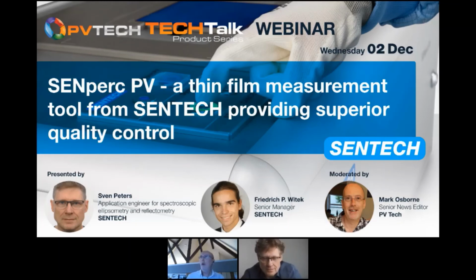Okay. Well, looking at the time, maybe just a few quick questions that I can fire at you. So obviously, the system uses a xenon lamp system. What's the kind of lifetime expectancy of this? And is there other sort of major consumables associated with the SENPERC tool? Yeah, so the lamp itself is the main consumable here.